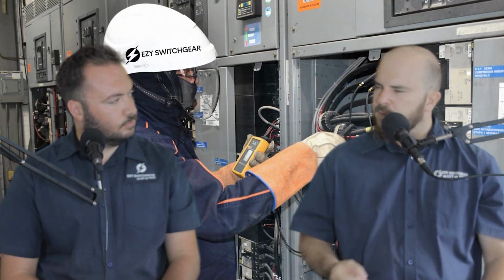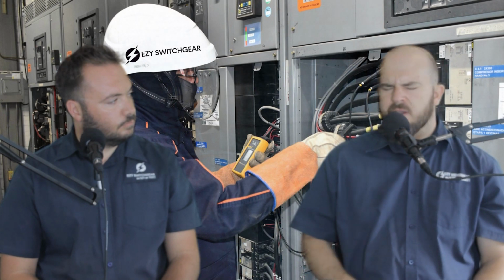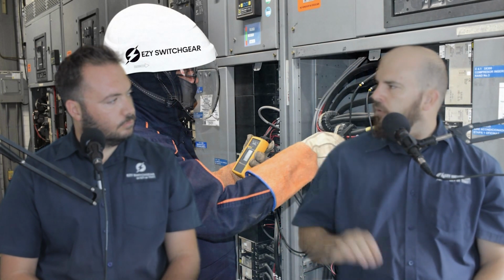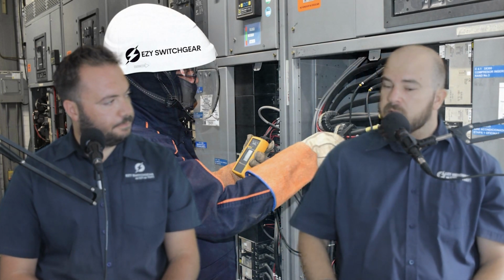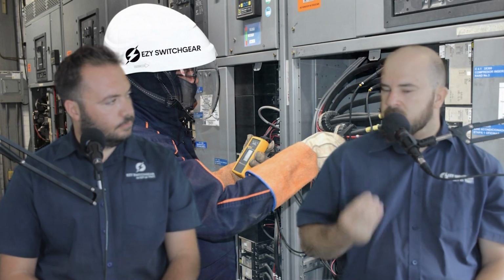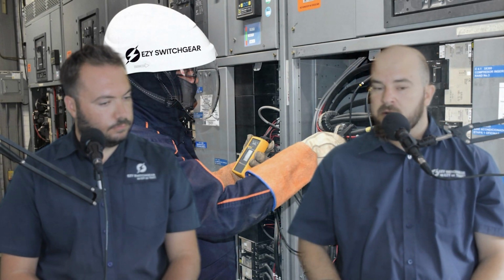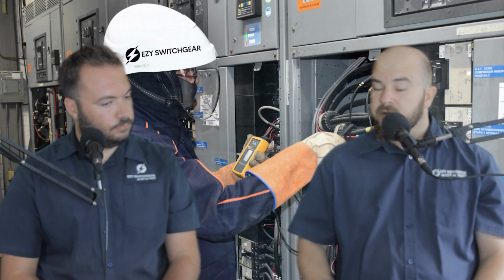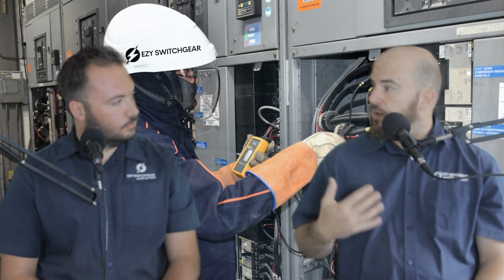The old subs, we have the old non-arc proof switchgear, you have to switch every time with your flash suits, because the risk of something happening is just so high. And when primary switchgear or even secondary switchgear explodes, you don't want to be close.